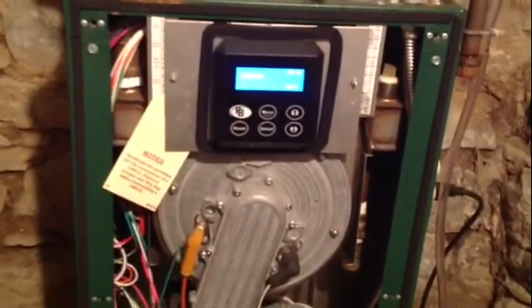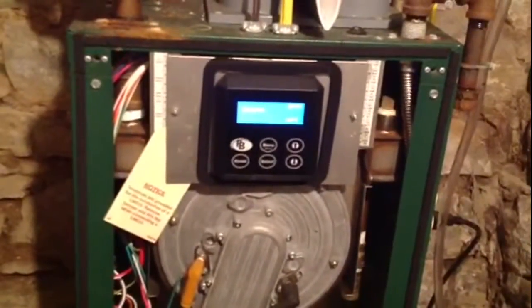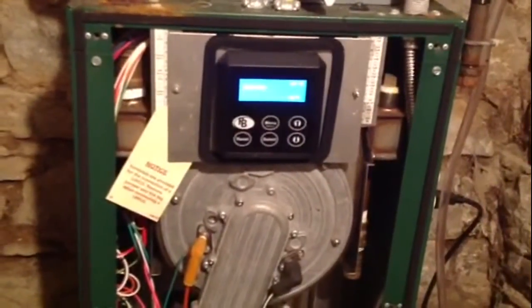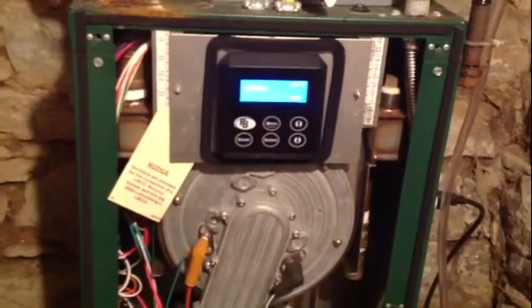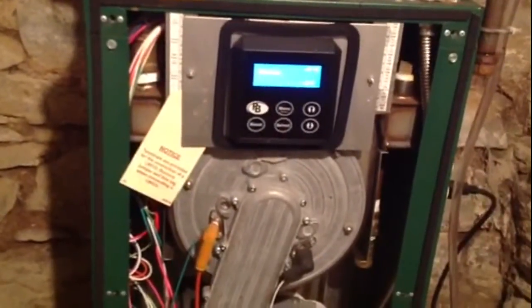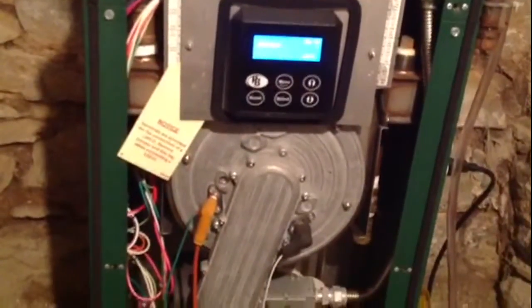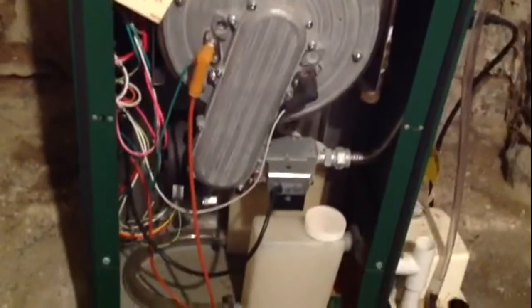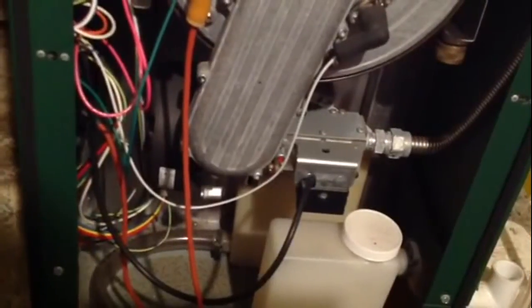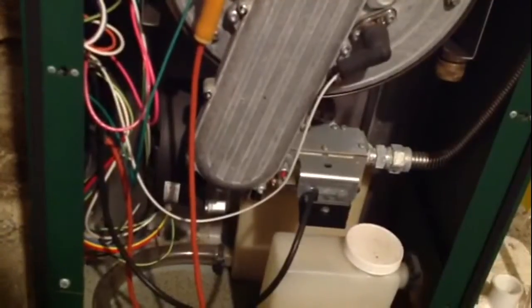Even though it has very nice options and you can tailor it depending on the needs, I'll be honest — I probably prefer an 85% furnace with a lot less maintenance, even though it's a little less efficient. I still think we're not quite ready for these 95% boilers yet. If I had to do it over, I probably wouldn't install this, basically because the parts are all custom — all different stuff than you would normally see in a boiler. So for me, I would go with an 85% boiler.